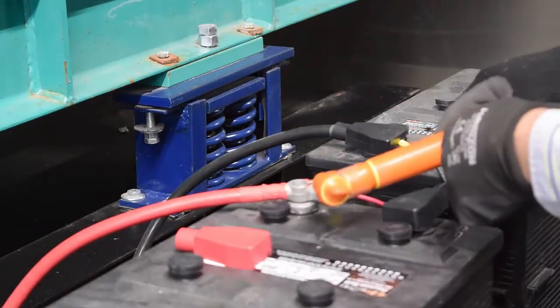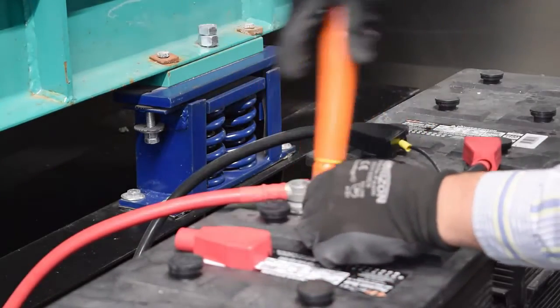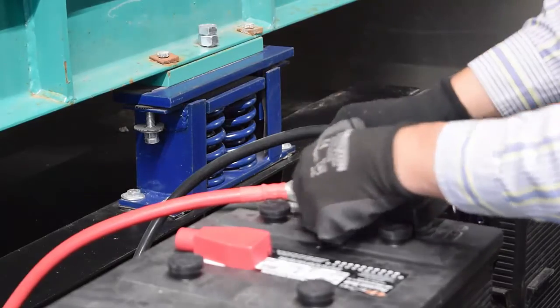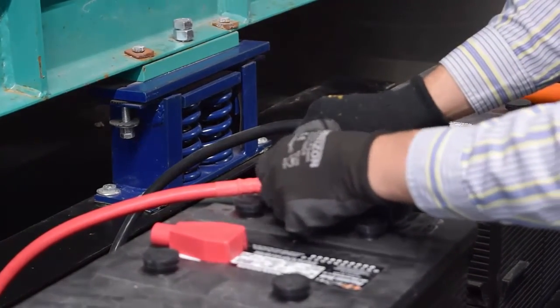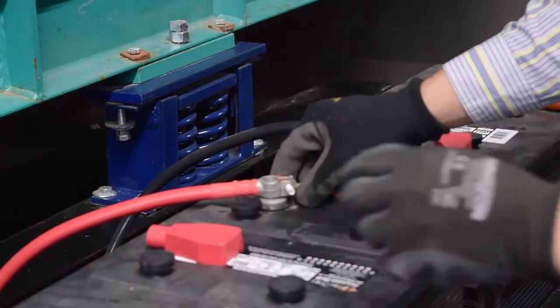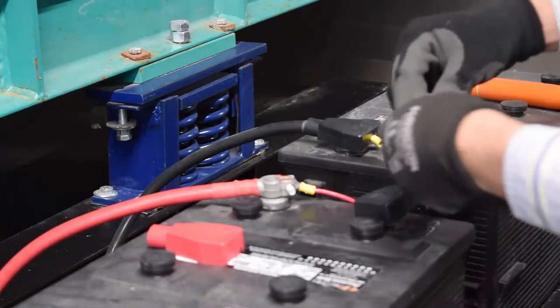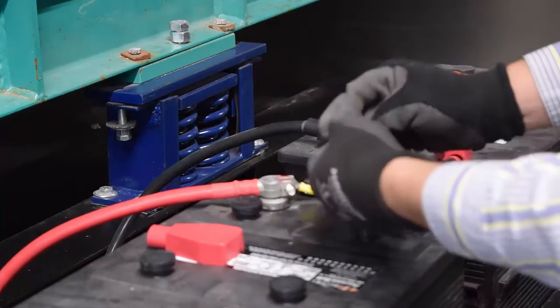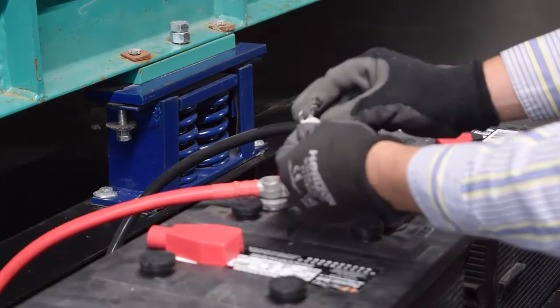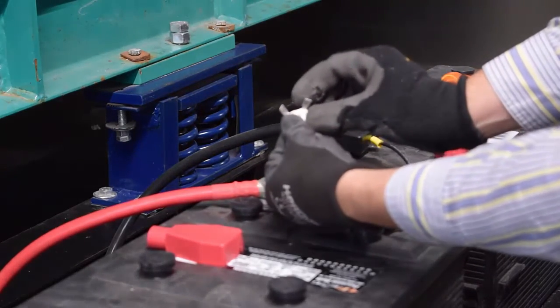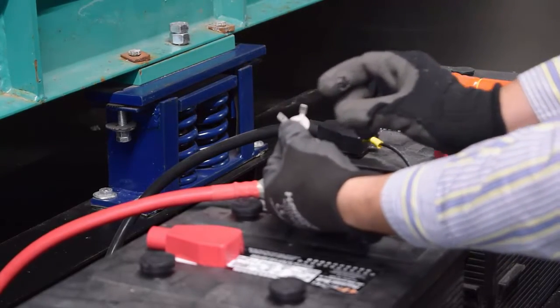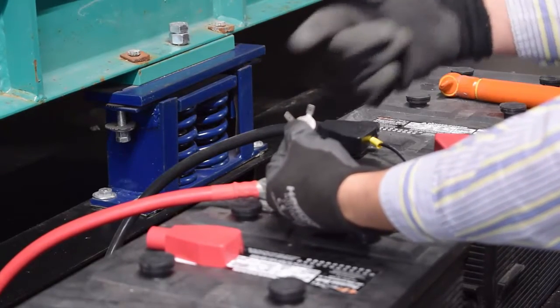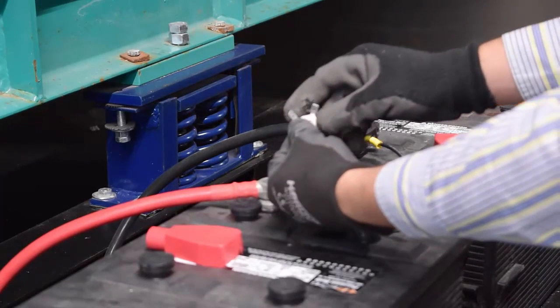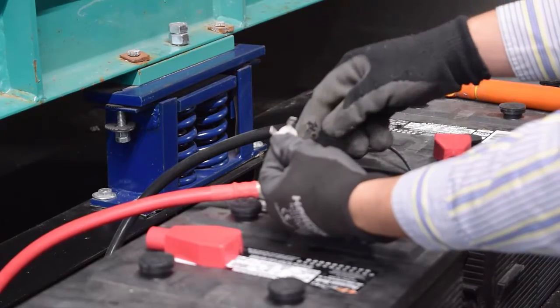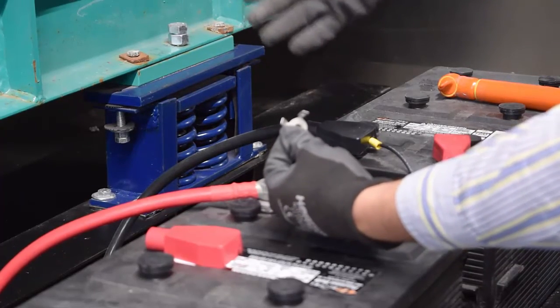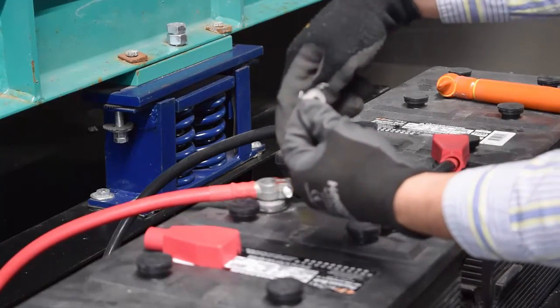So I'm going to use my insulated torque wrench and open up the connection here. And insert 2 tab washers and the positive power lead. Now I'm going to make sure that when I install these 2 tab washers that they're 90 degrees apart like this, because that will help to suppress electromagnetic pickup, and it makes it easier to connect and disconnect the quick disconnect terminals. And when you connect it in, make sure to place the tab washers below the flat washer and lock washer if the terminal has one.